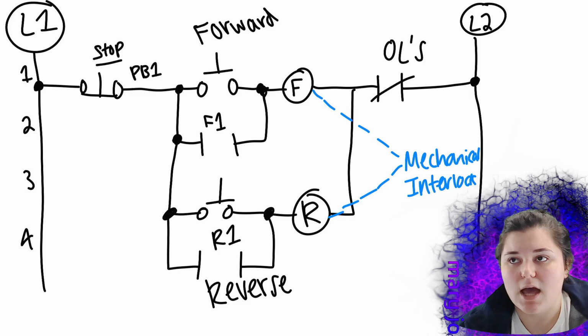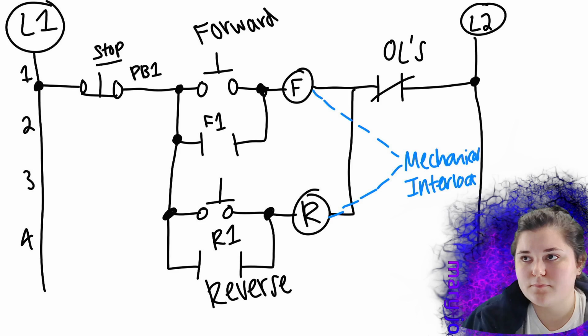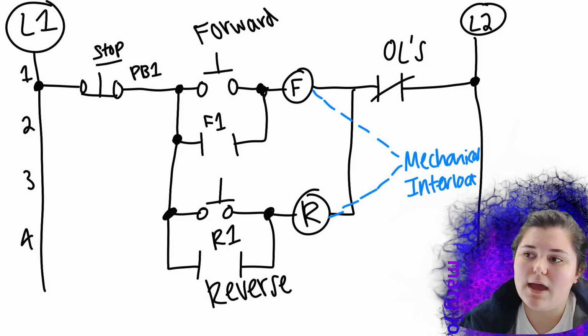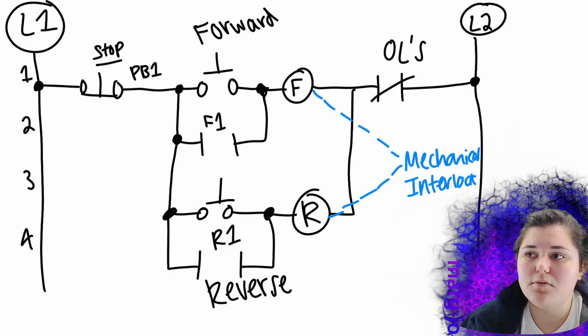So this is just drawing it out, what it should look like. You can see that your stop is your push button 1. And then moving on, you have your forward, where F1 would close, and your forward would become energized. And then you have it designed to where if your R1 closes, your reverse would become energized and your F1 would open. So you have to wire those up to where if one closes in, the other opens, and you cannot close in the other. And then you have your overload protection before you go to your motor.